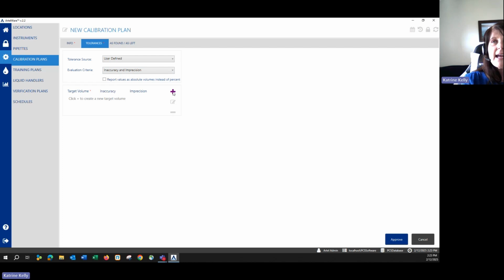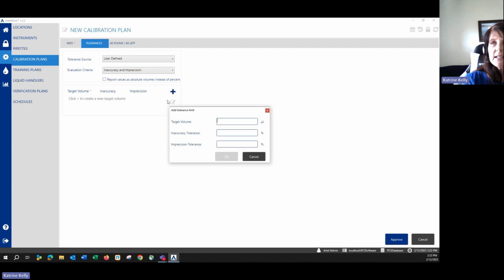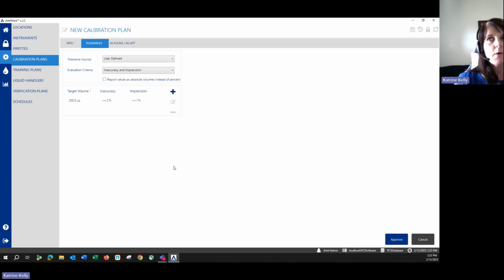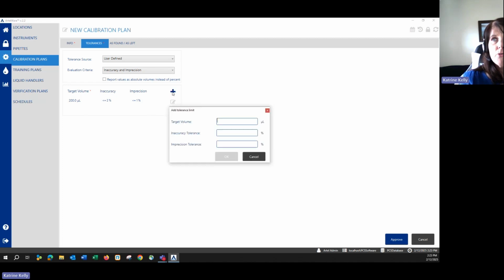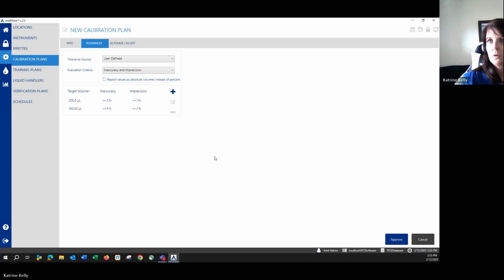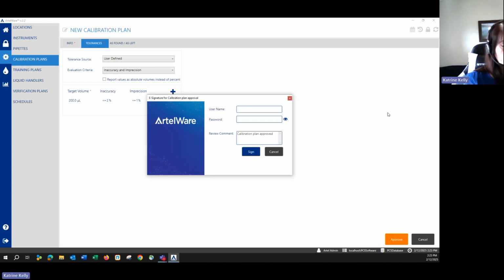So for user defined, I need to enter in my target volume and my inaccuracy and imprecision. So I have my pipette. Let me just double check the volume. I have it at 200 microliters. And then my inaccuracy is 2% and my tolerance will be 1%. Now, if I were going to also calibrate this pipette at the mid and low volumes, then I would also enter those in here. Just like that. So all 3 volumes, if I entered them in, will appear on the same report. And then once you have all of your volumes and tolerance limits entered in, you'll click Approve and enter in your credentials.